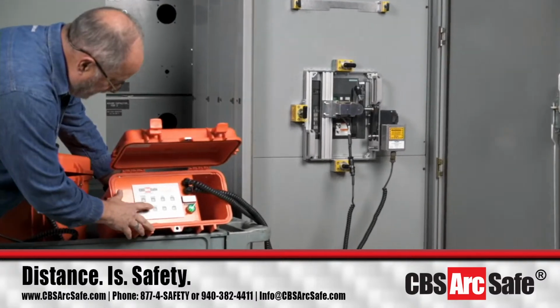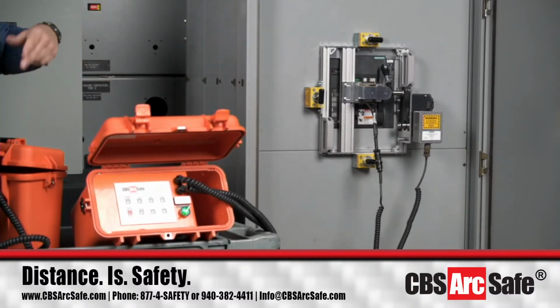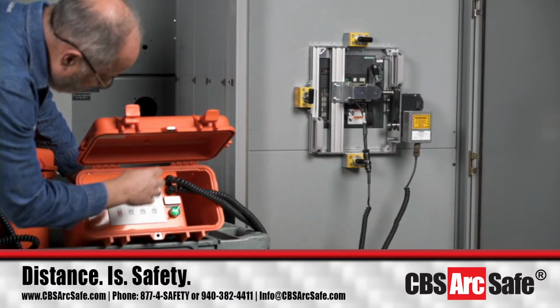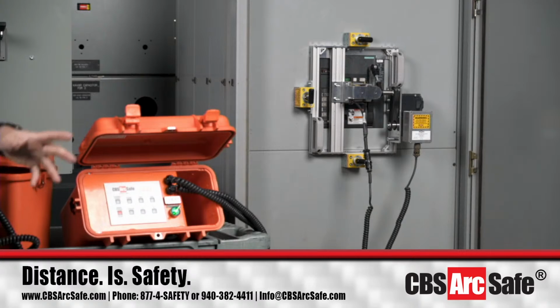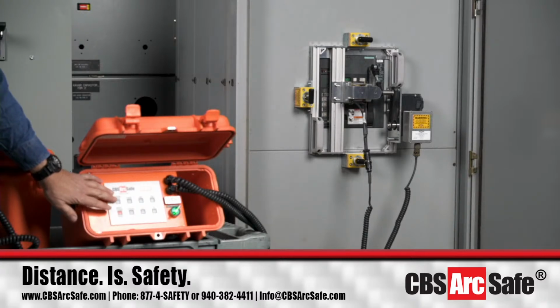All right, so we've got our cycles set at 9 because it takes 9 strokes for the RSO to be able to charge the breaker. Our T1 is set up at 5.4 for the strength of pulling it down. Our T2 is set up to 4.9. So just to explain, if you haven't seen an RSO 3 before, charge close is labeled that because you're going to see charge, you got close, and you got trip. Well, the 3 that we're going to play with today are going to be these 3.